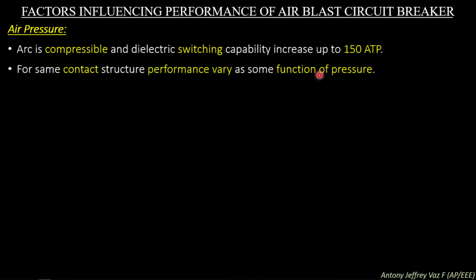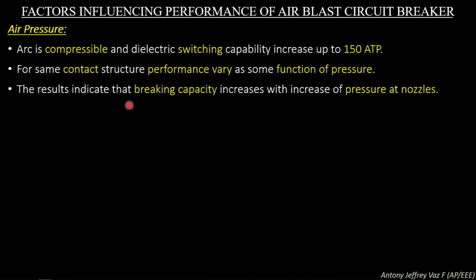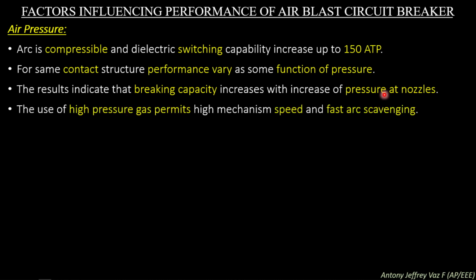So, the contact structure, that is, the metal contacts in closed position or in open position, their structure affects the function of pressure as well as the performance. The result indicates that breaking capacity increases with increase of pressure at the nozzle. So the breaking capacity will increase when the pressure at the nozzle gets increased.